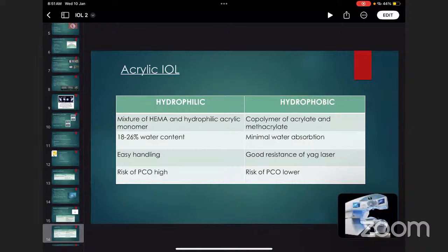We use mostly acrylic IOLs, hydrophilic and hydrophobic. Hydrophilic is made of mixture of hydroxyethyl methacrylate and hydrophilic acrylic monomer. It contains 18 to 26% water, easy handling, with high risk of posterior capsule opacification. Whereas hydrophobic is made of co-polymer of acrylate and methacrylate, minimal water absorption, good resistance to YAG laser, and PCO rate is lower.